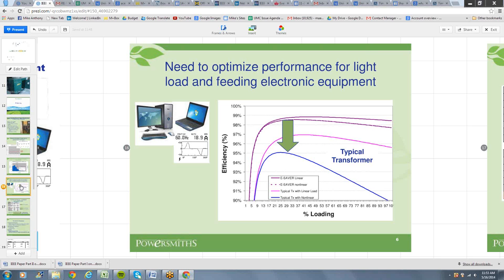And as a function of that, the efficiency of the transformer is further decreased, right? So now you're talking about a transformer that, if we look at the blue line, that's the operating efficiency of a typical transformer under nonlinear load compared to the line above it under linear load. So you can see that there's a gap there and that quick drop off.